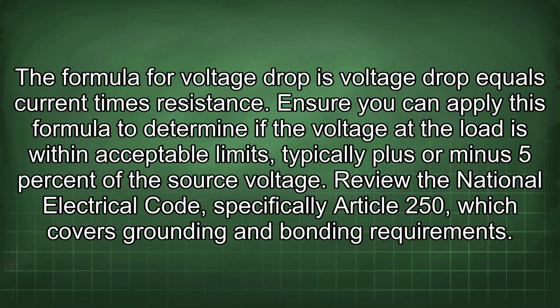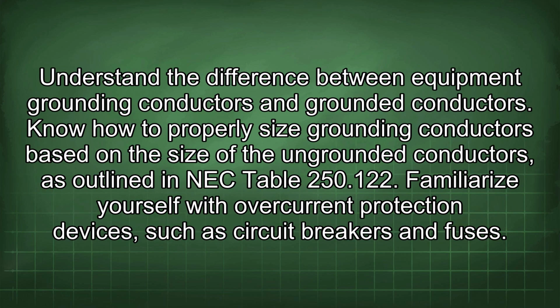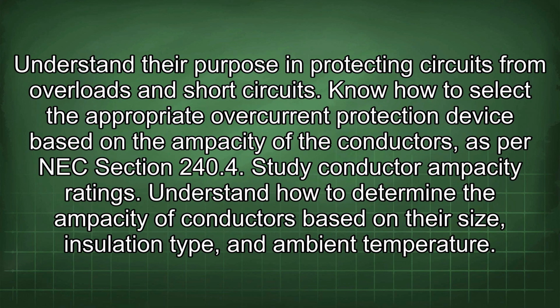Review the National Electrical Code, specifically Article 250, which covers grounding and bonding requirements. Understand the difference between equipment grounding conductors and grounded conductors. Know how to properly size grounding conductors based on the size of the ungrounded conductors, as outlined in NEC Table 250.122. Familiarize yourself with overcurrent protection devices such as circuit breakers and fuses. Understand their purpose in protecting circuits from overloads and short circuits.